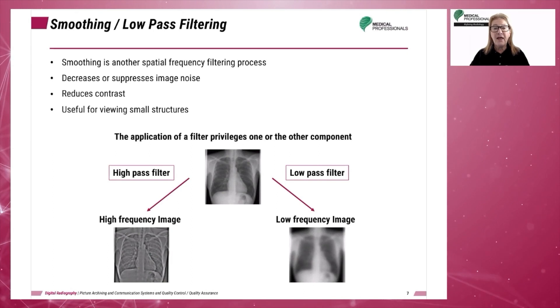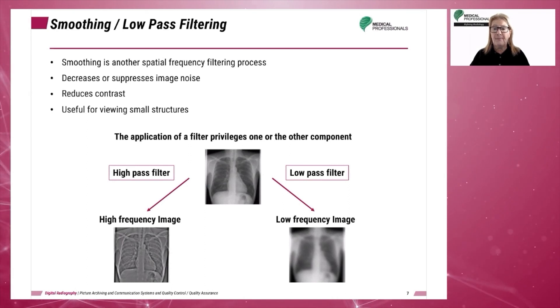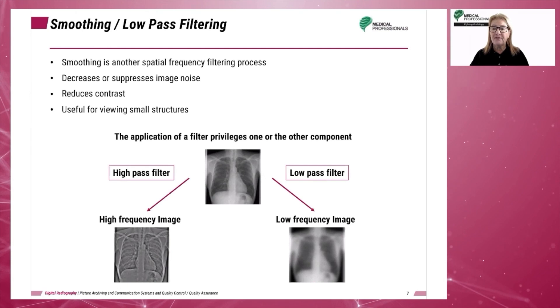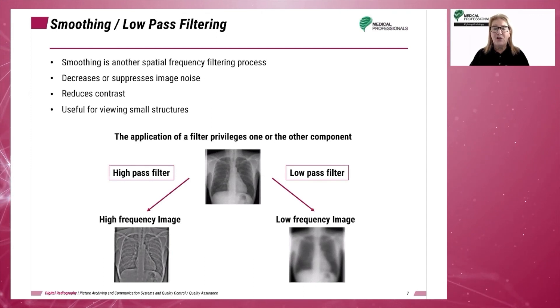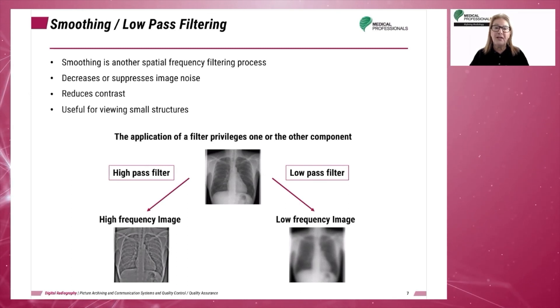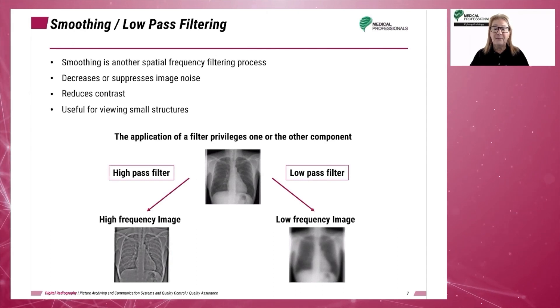Smoothing is another software function that removes high frequency noise from the image. In edge enhancement, the number of pixels averaged is reduced, whereas with smoothing, the number of pixels averaged is increased. Smoothing is the result of averaging each pixel's frequency with surrounding pixel values to remove high frequency noise. The more pixels involved in the average, the smoother the image will appear. This process reduces noise, contrast, and image detail.